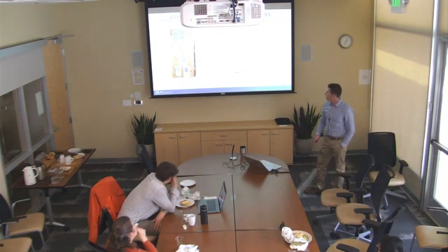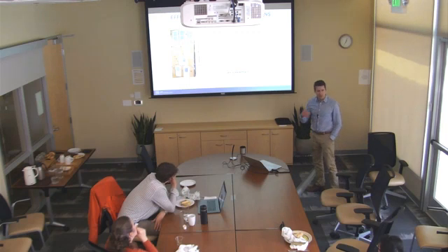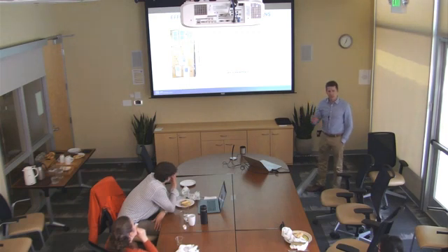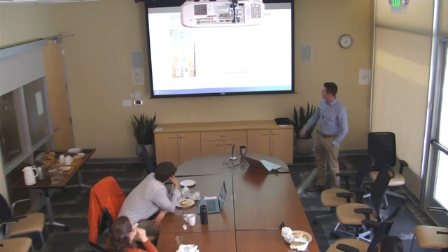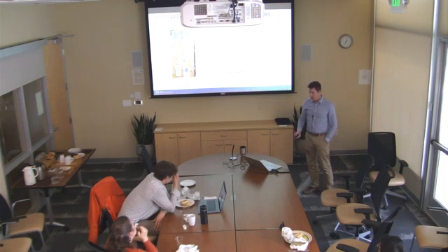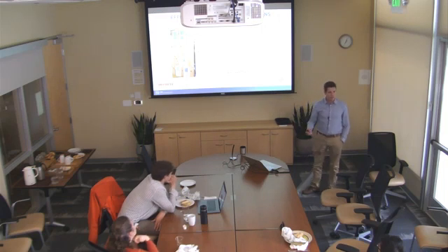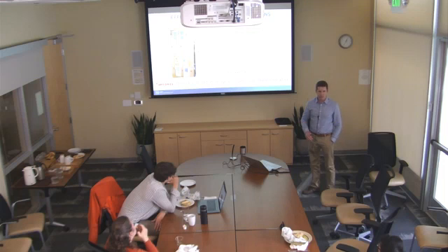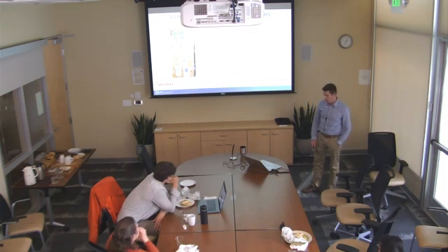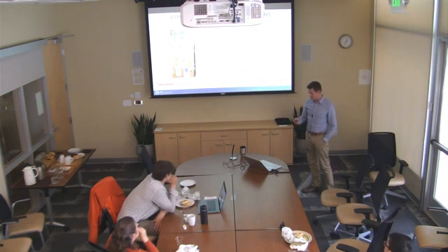Okay, so in our lab, we were able to measure every individual duct run. So this is the delivery effectiveness of each grill that I showed in the picture. The grills are shown on the left there. As you can see, each grill is not treated equally. They have different performance. And what you'll also notice is that as you reduce speed, you change the balance of your system. So the amount of airflow through each grill, or relative amount of airflow, changes between the different ducts. And the performance is different between each of them.